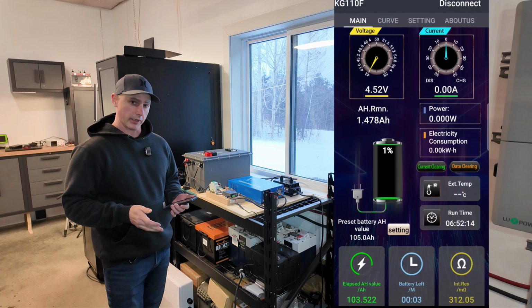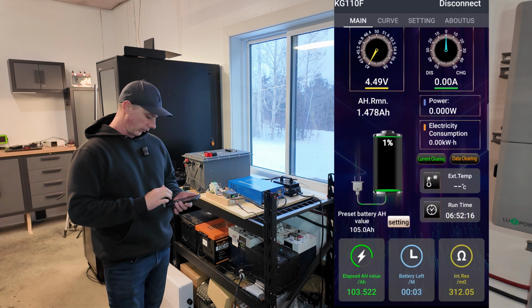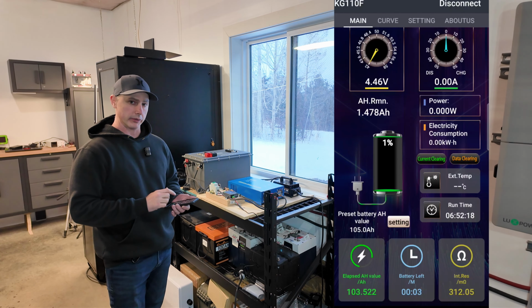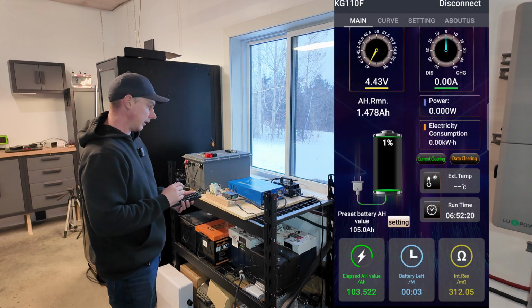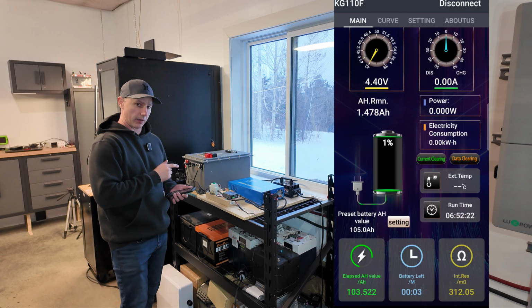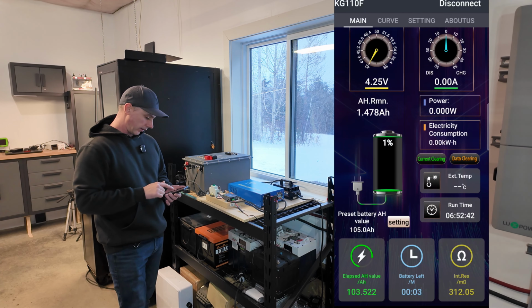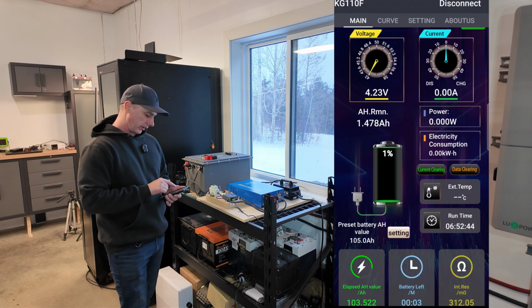And you can see there, we're done the discharge test and we got 103.522, which is lower than the stated 105 amp hours on the battery. You can see there we have disconnect, you can tell by it only showing 4.22 volts there.